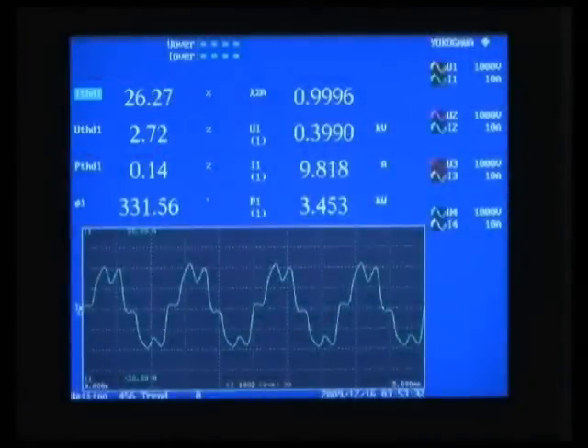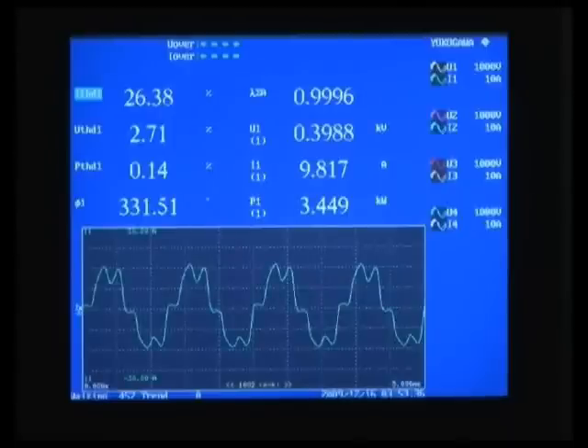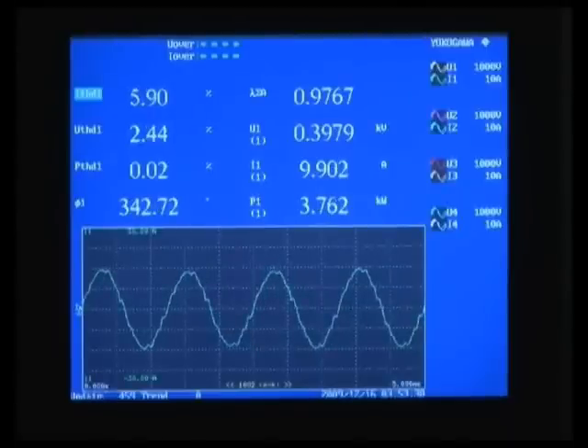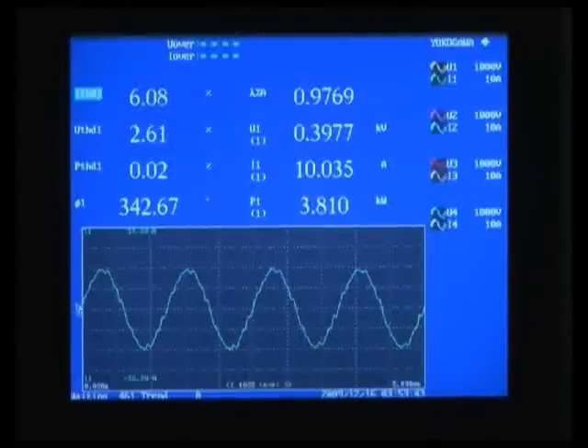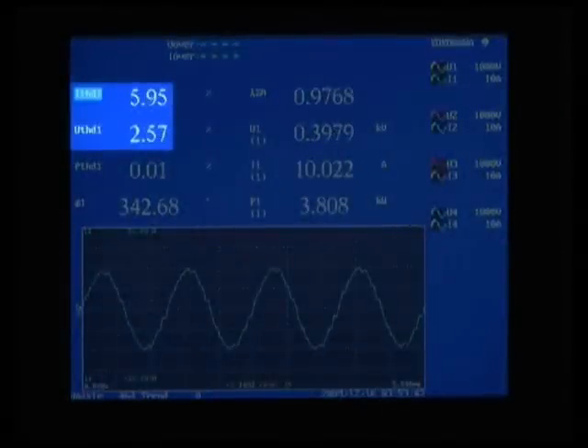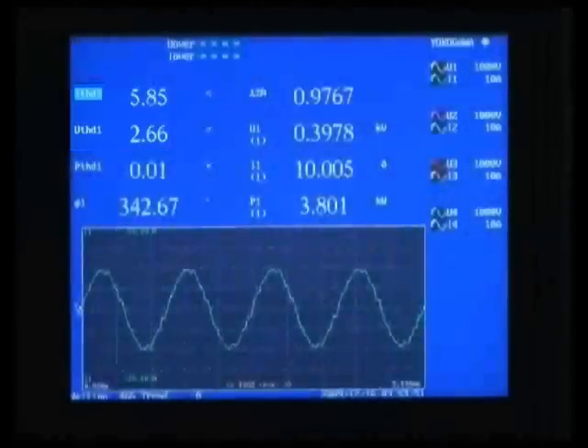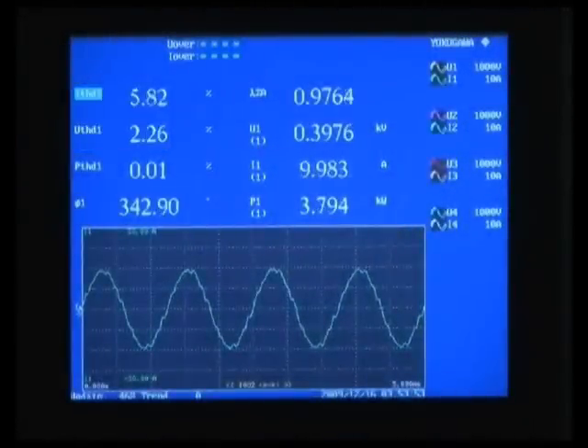Going to take the next step up, going from 6-pulse with inductor to 18-pulse. Now the harmonic analyzer is stabilized, and we've seen in the area of 6% current distortion and about 2.5% voltage distortion. Taking a look at the waveform itself, we are really getting close to a sinusoidal waveform.